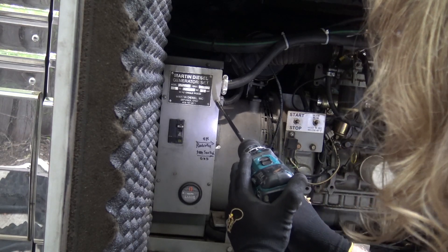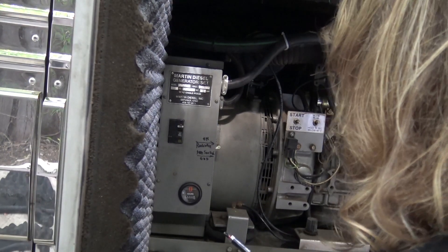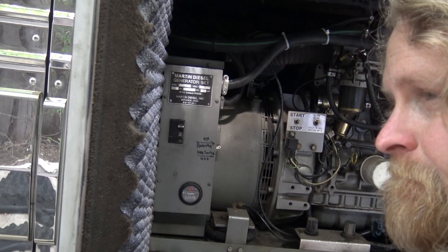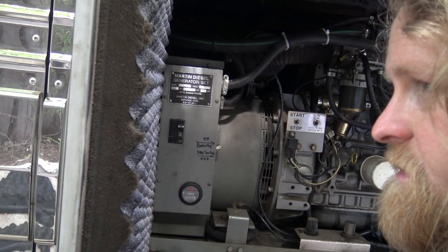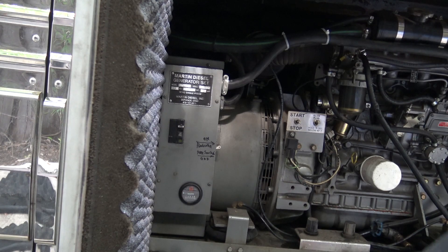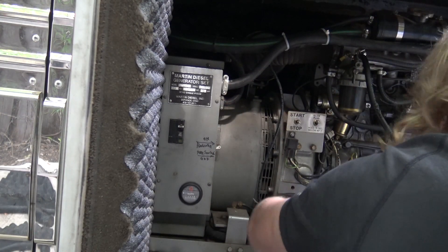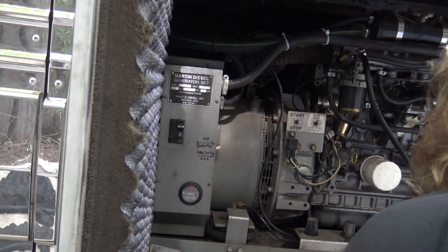This is a Martin diesel generator set. It's single-phase 16 kilowatt, so I'm running it into two 5-kilowatt inverters. I don't know if that's going to be a problem, but this only puts out 66 amps per side and my inverters only accept 60 amps. So when I'm running the generator I think I might have a little excess heat — I'm going to have to look into that. Let's just finish this off and move forward.